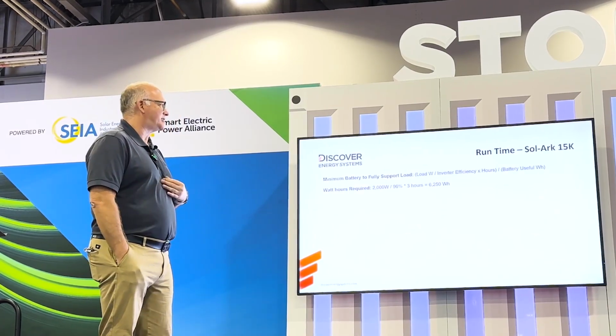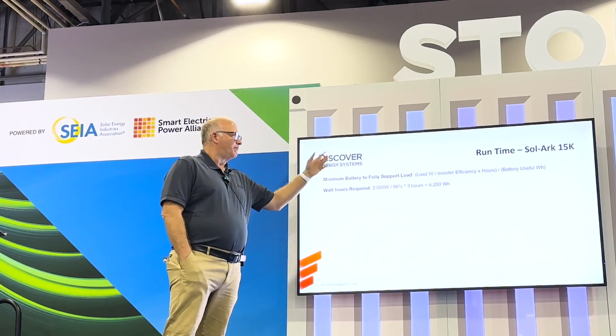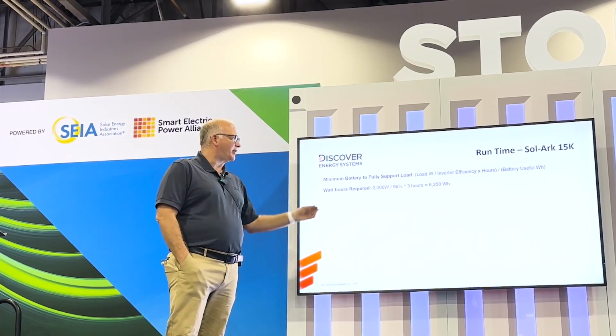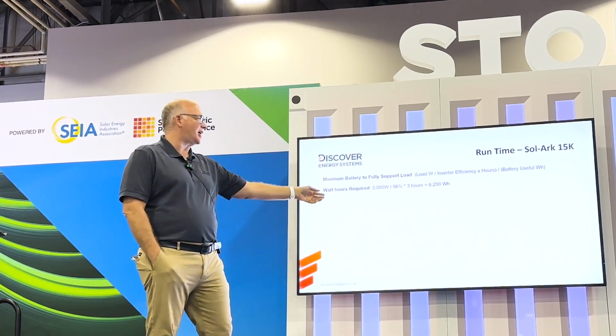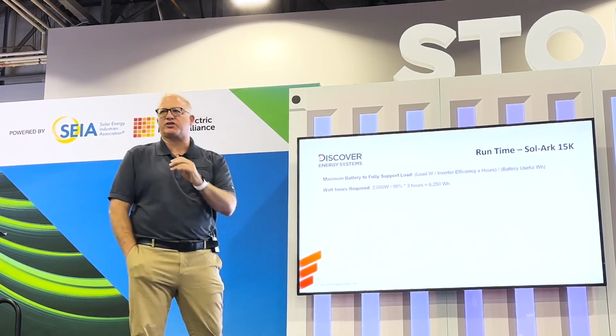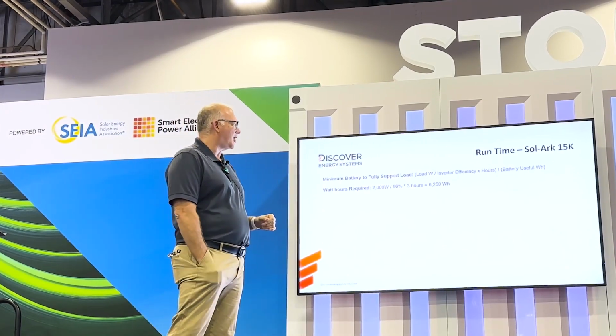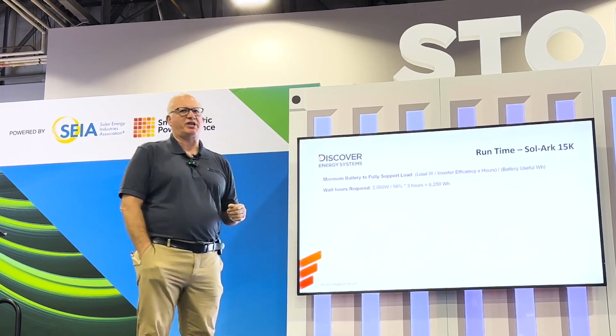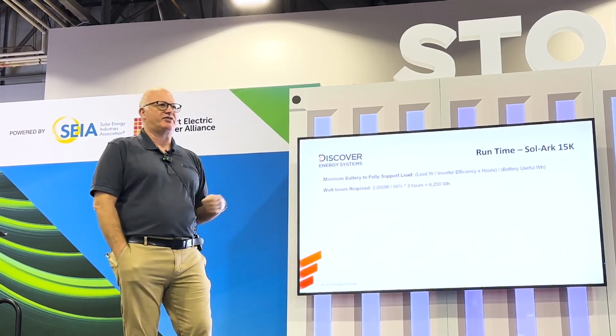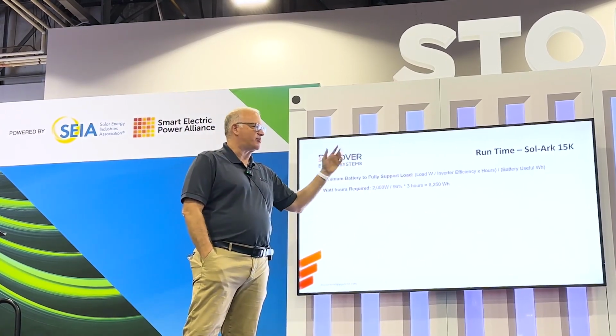So runtime. I looked at the Sol-Ark product and made a call: I selected a 2,000 watt load, which is quite small but serves our example. Divide by 96%, that's the system efficiency, times 3 hours. If I do that, I would need 6,200 watts.